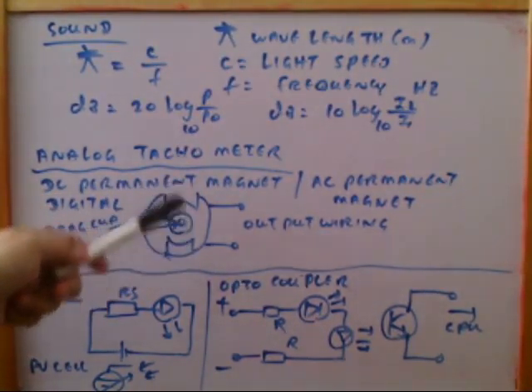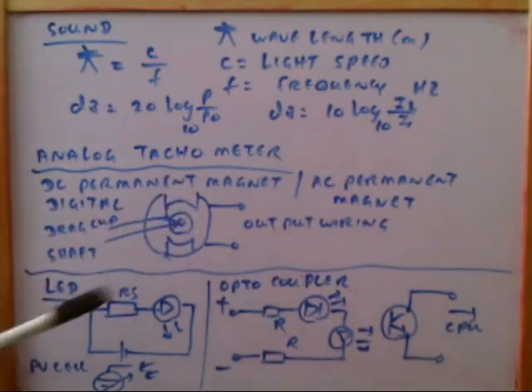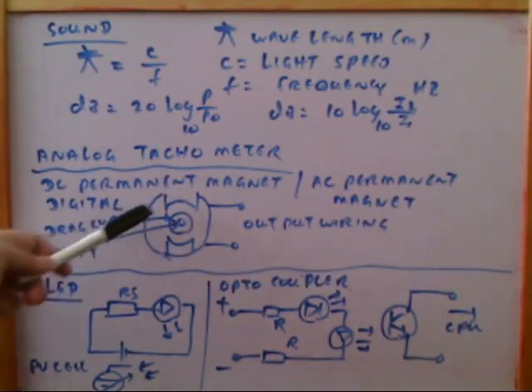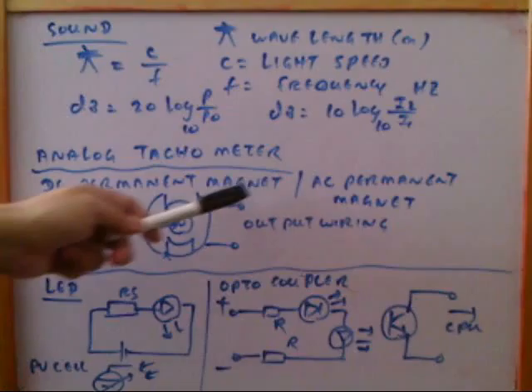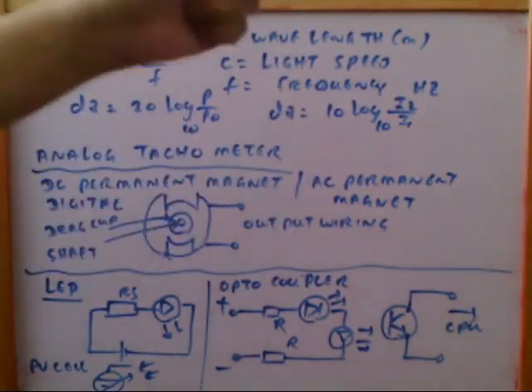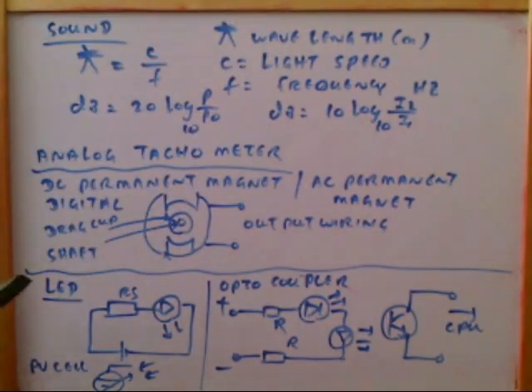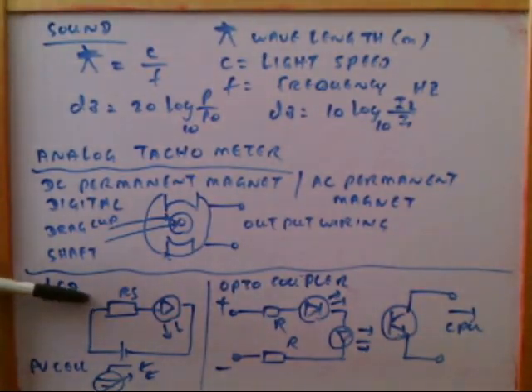So this electric, the electromagnetic coil, here is the shaft, here is the drag cup. When this one rotates, output voltage will be coming out. So depending on the speed, depending on the shaft speed, output voltage coming out. This output is sent to the controller.